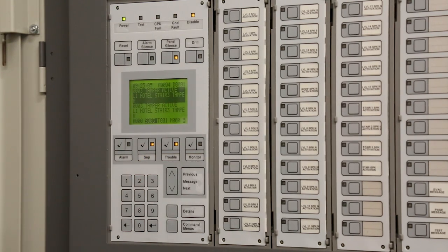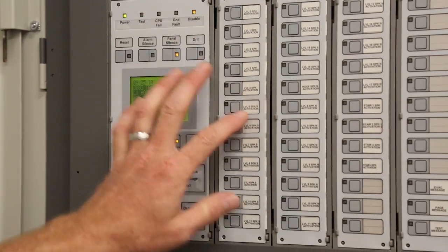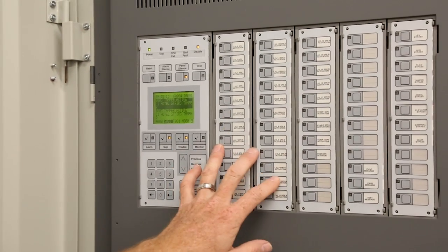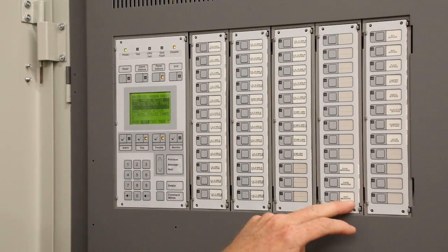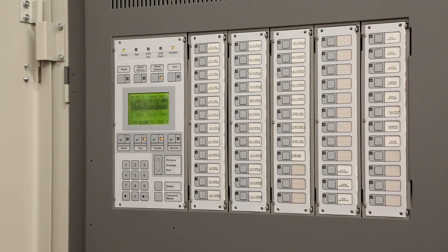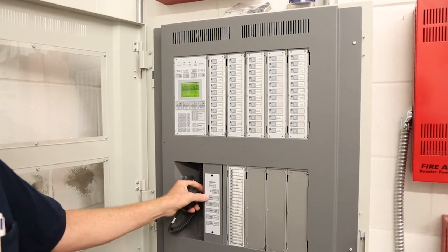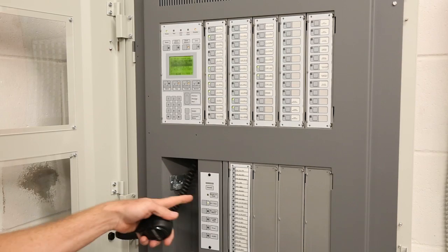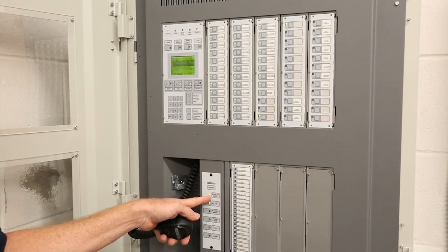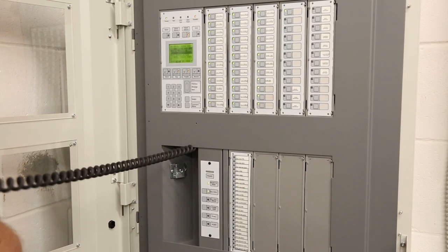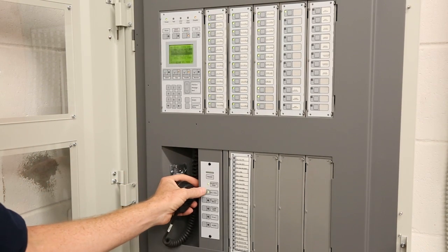I guess if we wanted to do an announcement, we can select the button here. You can hit page message and select what floor you want to go to. Or we have a test message for when we're doing testing or evac. Or if you want to talk to everybody on every floor, basically hit all call right here, key the mic, wait till that's picked. You notice all these lights are lighting up, everything's picked right now. Test 1, 2, 3, so it's going through the whole place. It doesn't set an alarm first? No.